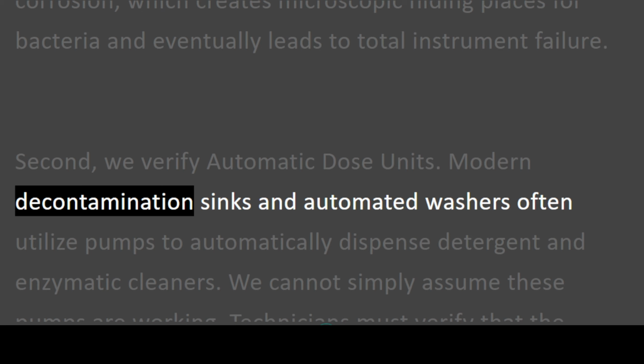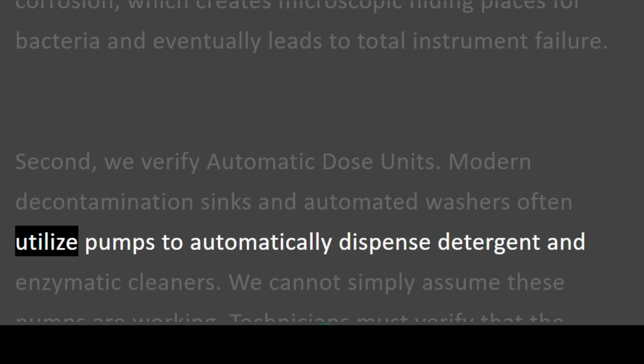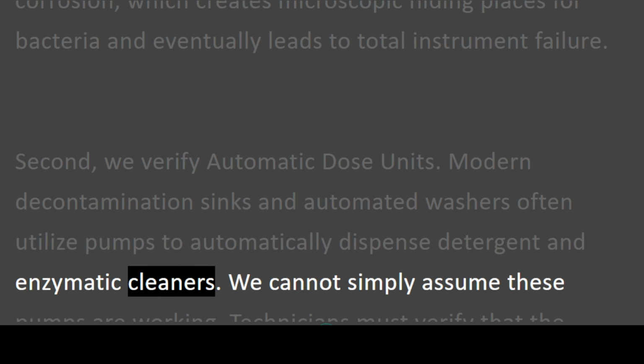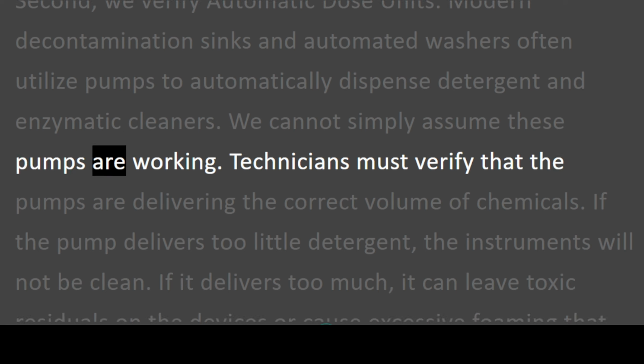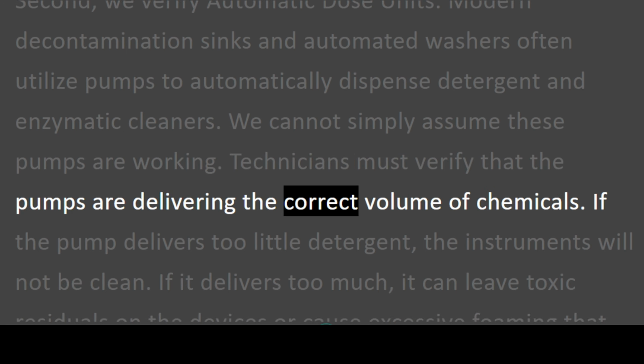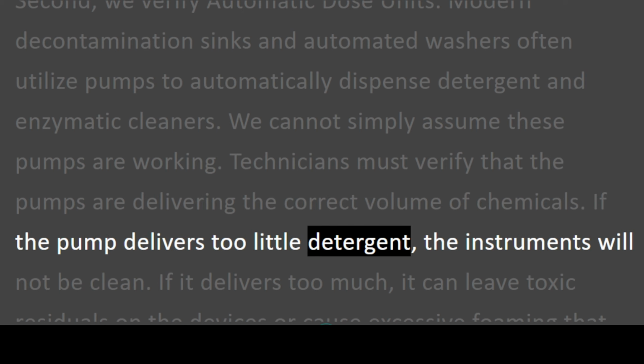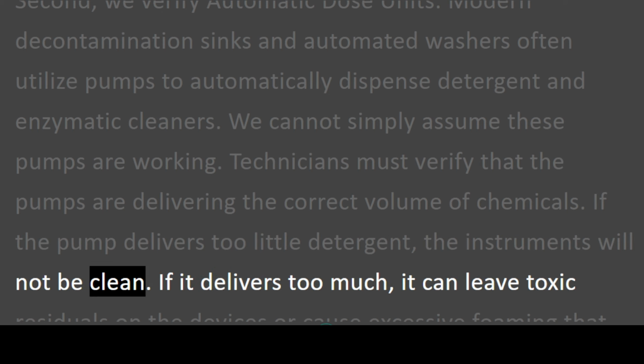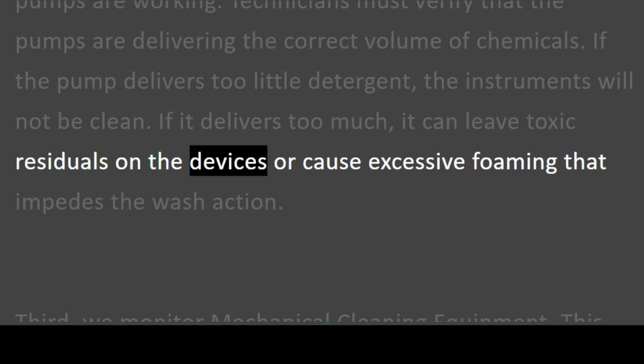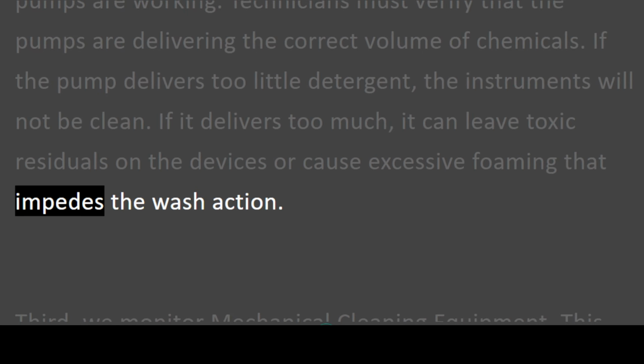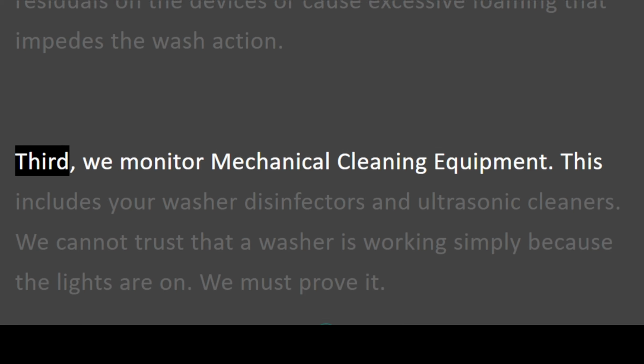Modern decontamination sinks and automated washers often utilize pumps to automatically dispense detergent and enzymatic cleaners. We cannot simply assume these pumps are working. Technicians must verify that the pumps are delivering the correct volume of chemicals. If the pump delivers too little detergent, the instruments will not be clean. If it delivers too much, it can leave toxic residuals on the devices or cause excessive foaming that impedes the wash action. Third, we monitor mechanical cleaning equipment.